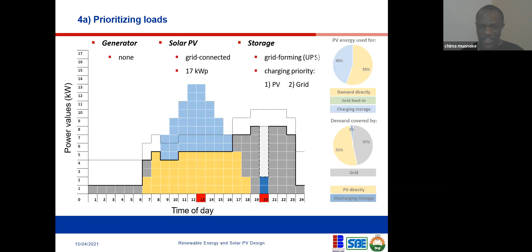Now this is just a worst case scenario, where the sun did not come out very well. When designing, you normally take into consideration the day the sun doesn't come out, and size your battery to supply the energy required for that day. But imagine there are loads you can shift, or appliances you can avoid using on that day — that means you can reduce the size of your battery. And when you reduce the battery storage size, you're definitely going to save the cost of that project, reducing its overall cost.